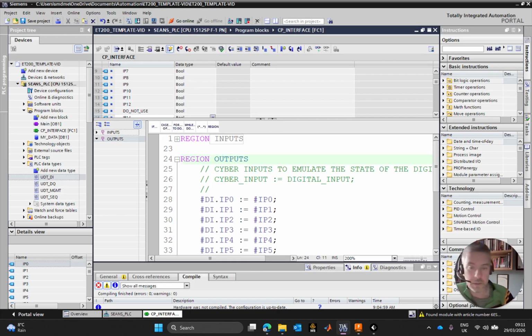Okay, so in this one here, this is going to be digital output. So we reverse the order here. In my code, I read what's happening in the outside world. The outside world information comes in, if the signal is extended, if the button's been pressed, whatever it might be. I read that and transfer it into a cyber signal, a cyber piece of data, and my code reads the data. Then I make decisions in code based on it, and I write a response, what the code should do, in a digital cyber piece of data.